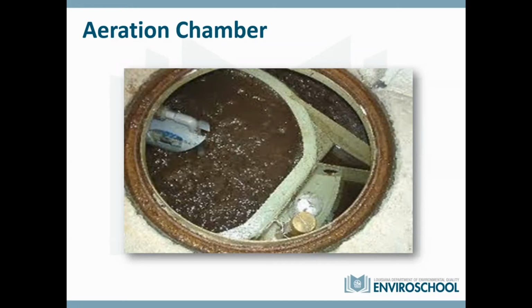What he told me was that's what you're looking for. If it's a brownish earthy tone and it has an earthy smell to it, that means your aeration chamber is doing what it's supposed to be doing. So keep this picture in mind if you haven't seen something like this before, because this is what you're looking for.